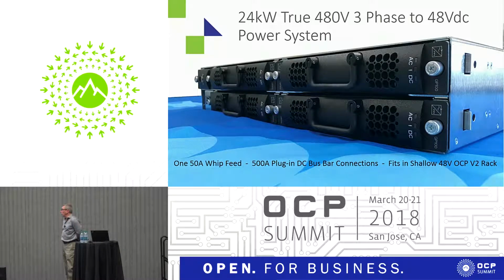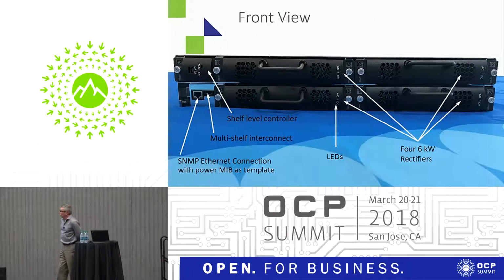You can see here we've got 4 plug-in modules. There are screw retainers to keep them in place, but the shelf itself can be installed with minimal effort without the rectifiers in. If you put the rectifiers in first, it's pretty heavy, but the shelf itself is pretty easy to install, and the fact that it clips in rather than bolts in helps that as well, of course. From the front, you see on the left there's the controller in the top left slot. Below that is the communications port.